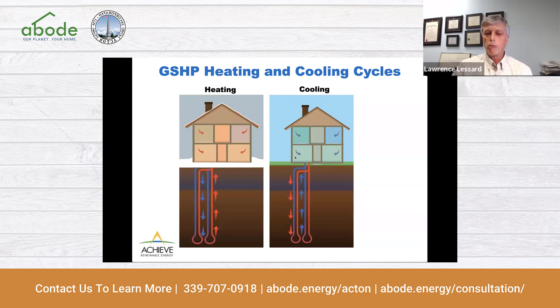So with an electric heating system, like an electric baseboard or an electric hot water heater, if you put a kilowatt of electricity into the hot water heater, you'll get a kilowatt of thermal energy. So what you get out is the same as what you get in. In heating and cooling, a common rating system is COP, coefficient of performance. And that's a simple ratio. What did you get out of the equipment? What did you have to put in? So with electric hot water, you've got 1 kilowatt out, you put 1 kilowatt in, your COP is 1. So everything that you bought in that 1 kilowatt of electricity, you get to use.